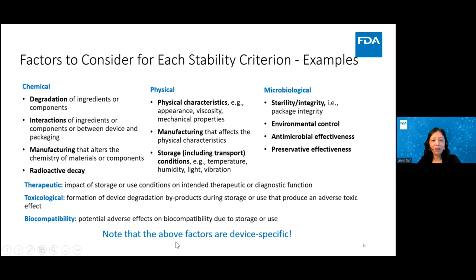Also for the physical criterion, I listed something like appearance. In some cases, a significant change in appearance may cause concern to the users, even though the performance of the device is not affected. I just want to mention that all these factors are device specific. To determine if and what shelf life testing is needed, it is recommended to perform a risk analysis. This risk analysis should be in accordance with the currently FDA recognized version of ISO 14971 for all stability factors that we mentioned earlier.